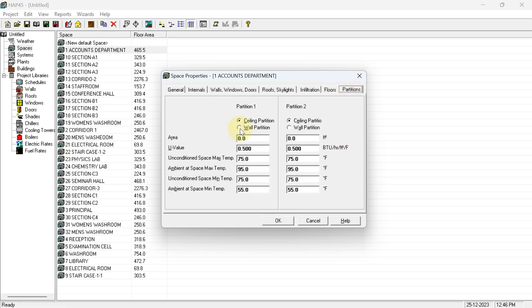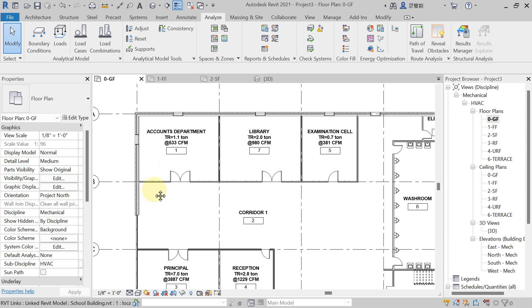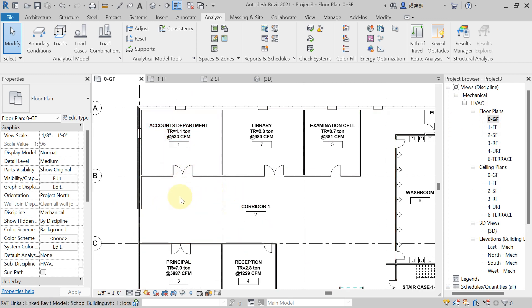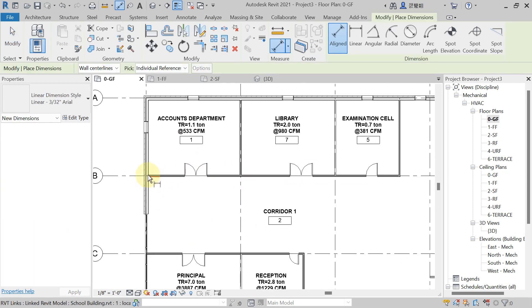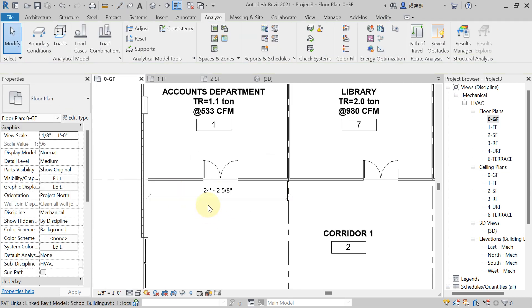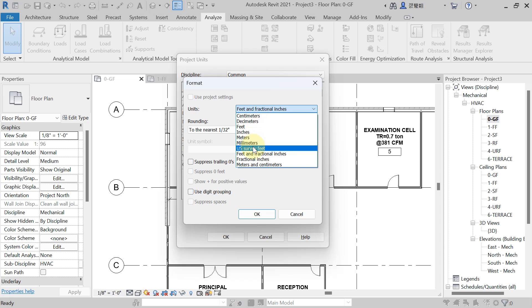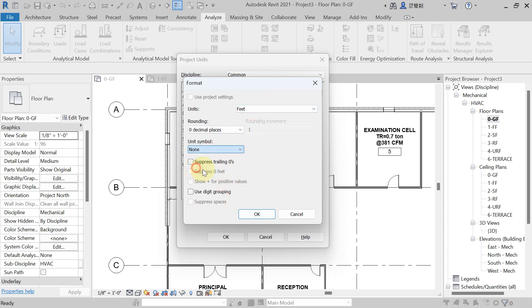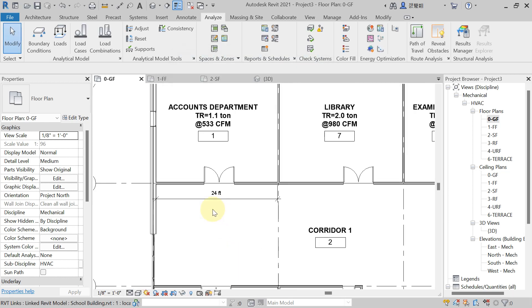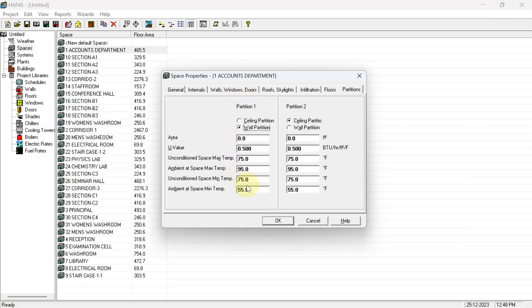Now come to the Partition tab. In our project we do have a partition wall — the wall between the conditioned account department and the unconditioned corridor. To confirm, open Revit and check the ground floor plan. Use the dimension command to measure that wall. It is showing approximately 24 feet in length. The ceiling height is 10 feet, so the partition wall area is 24 × 10 = 240 square feet.